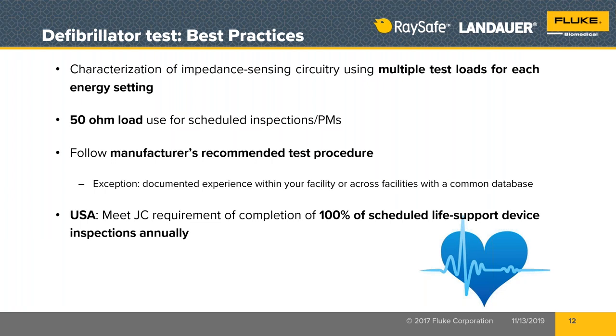Oh, the third situation for the testing would be if the doctor or the nurse doesn't feel that the output energy dialed into the defibrillator was fully delivered, they may have a complaint. You're going to go to the clinical unit. You're probably going to have to bring that defibrillator down to the shop to do the testing. And you're going to need to be able to repeat these tests and show, no matter what the load was, that the output energy was delivered. You need to know a little bit more about the incident that occurred that they were complaining about.